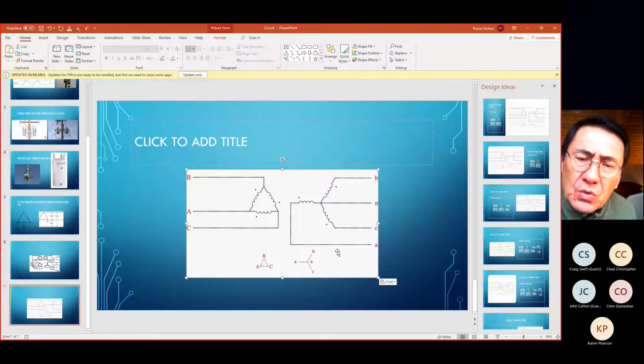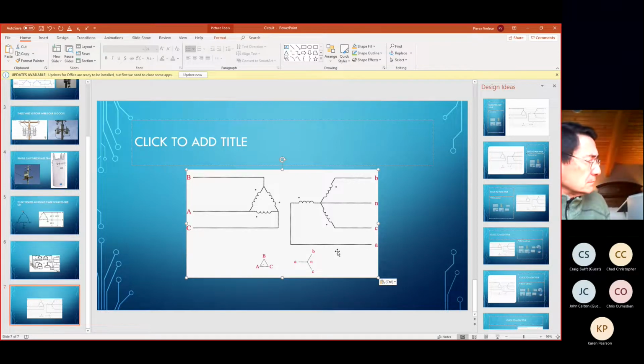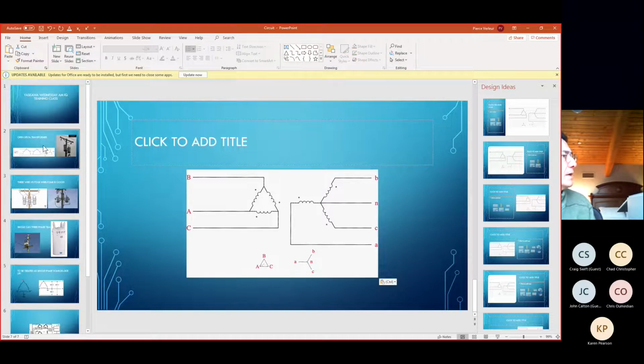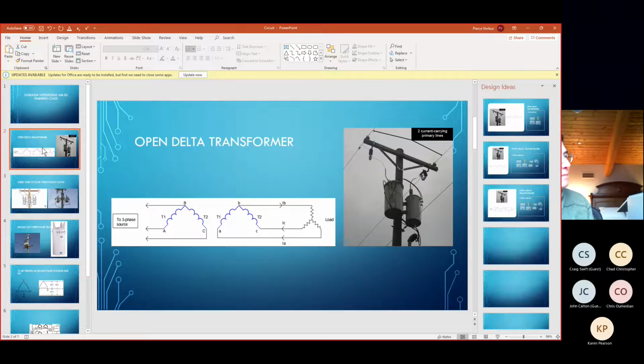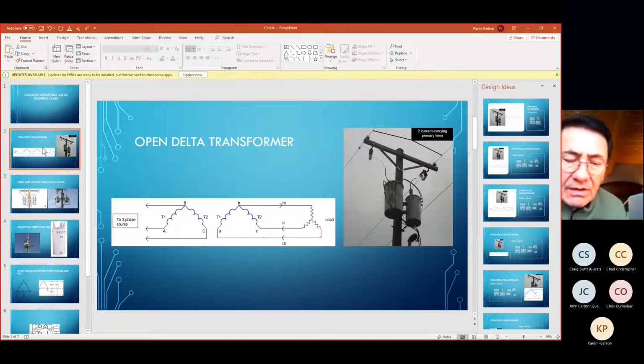Craig, are you seeing any more new installations coming out with open delta? No, in fact, PG is trying to force everybody to 460 so we can get rid of the problem. Which of course exacerbates harmonics. Now, is open delta primarily seen in 230 volt 3-phase applications? Primarily, yes. Okay, well, that's a good thing to note. So if we go back up, our discussion has been on open delta, and our recommendation is size up one frame size, not one size, to get the extra capacitors, and put 3% or 5% input impedance on the application.